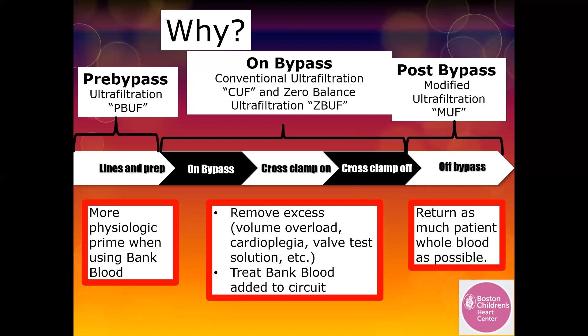Now, most often when I discuss hemoconcentration with other centers, I discover that they use passive ultrafiltration during the case, and also beforehand if they employ pre-bypass ultrafiltration. This diagram shows a typical setup. Note that the source of blood for the hemoconcentrator is post-oxygenator. The hemoconcentrator flow is passive and is determined in part by the overall system pressure. If you are doing a neonatal case or utilizing low flow, your hemoconcentrator flow and the ability to remove fluid will be limited because the driving pressure will be low. Also note that the flow through the hemoconcentrator in this arrangement is such that flow enters the bottom of the device and exits the top. Air is continuously purged to the reservoir.